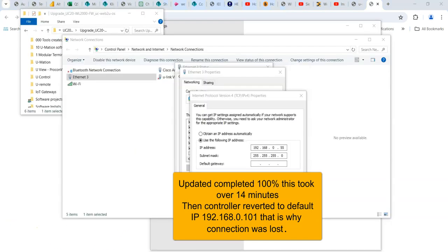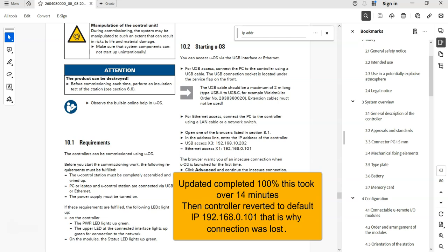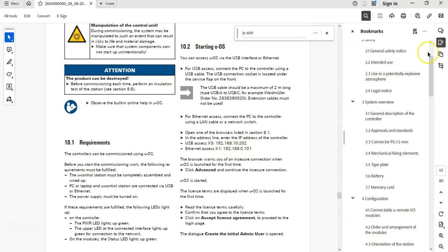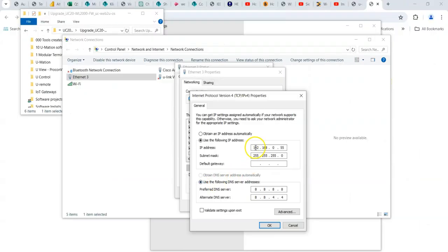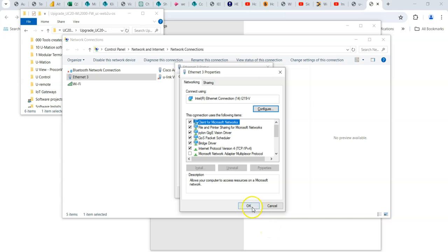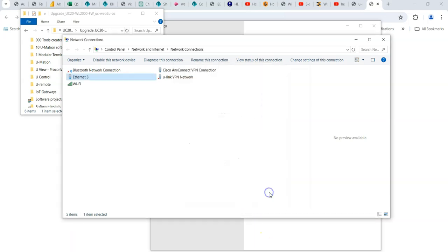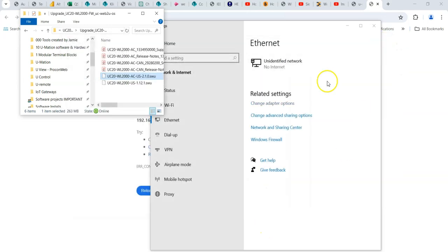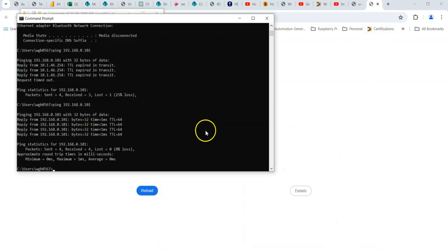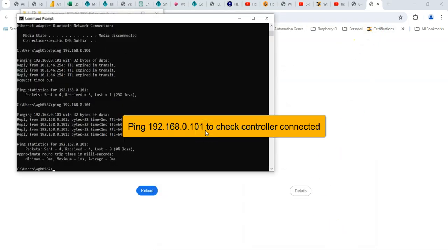Okay, so the default IP address of port X1, the top port, is 192.168.0.101. So I now need to pick an address for my PC in that range. So I'm going to use 0.55. Okay, close that, close all my network windows.